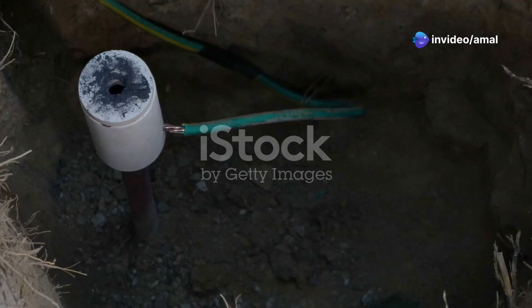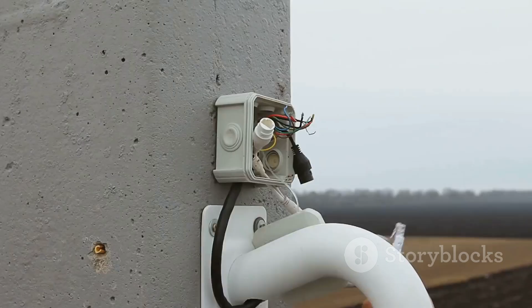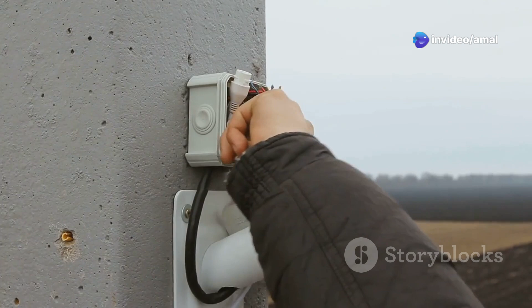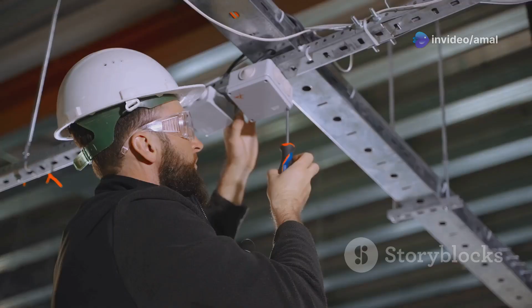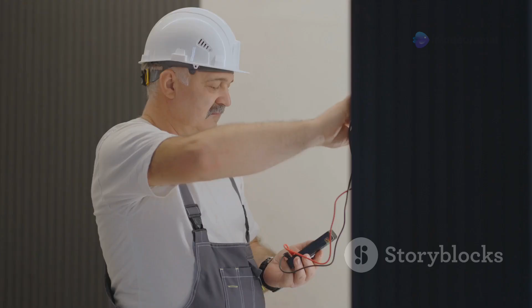In electrical systems, grounding refers to connecting a current-carrying conductor to the earth. This is typically done by connecting the grounding conductor to a grounding electrode, such as a metal rod driven into the ground. Earthing, on the other hand, refers to connecting non-current carrying metallic parts of equipment or installations to the earth.